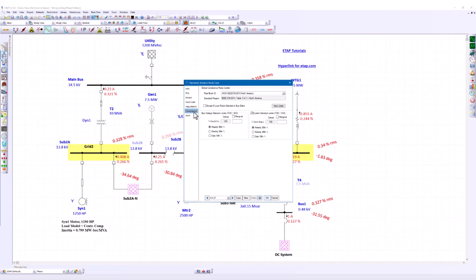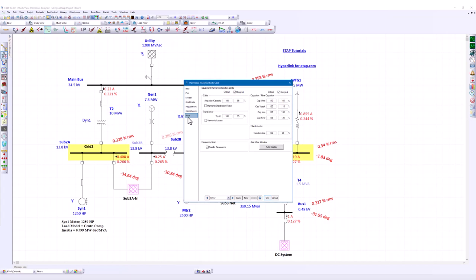First, in the compliance page, you will have the option to select which rule ID to go by. There is a checkbox if you want to accept certain locations connecting at different utilities or having different harmonic requirements. You can check this checkbox and specify a different rule in a corresponding bus editor. In the alert tab, you can define the critical and the marginal alert thresholds for cables, transformers, capacitor, and filters.